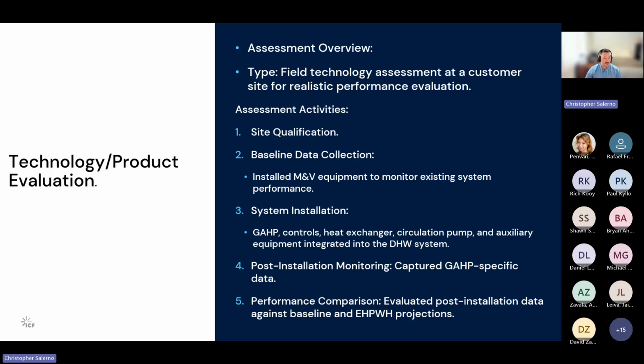So after we found the site, the first site for this study, we did the baseline data collection. So we started to install baseline monitoring M&V equipment, measurement and verification equipment, to baseline and monitor the existing boilers' water heating system performance. That consisted of inline turbine water meters, diaphragm gas meters, temperature probe sensors, and CTs, current transducers, to monitor the power. And so those were all being logged in real time on a minute level basis to be able to characterize the baseline that we have at the property.